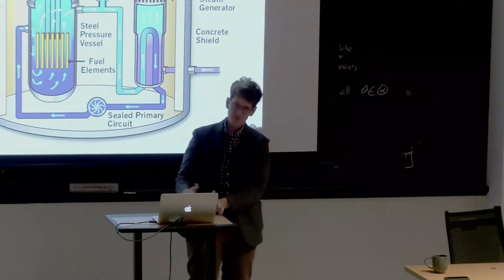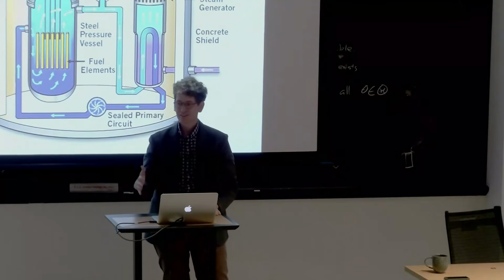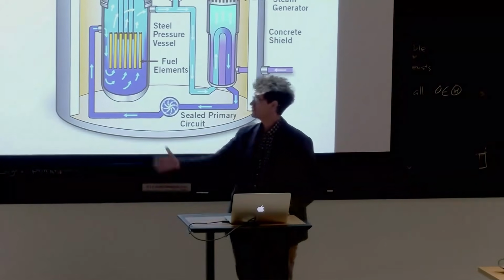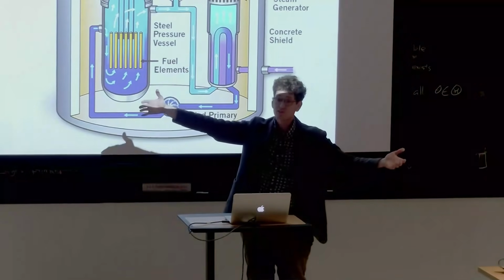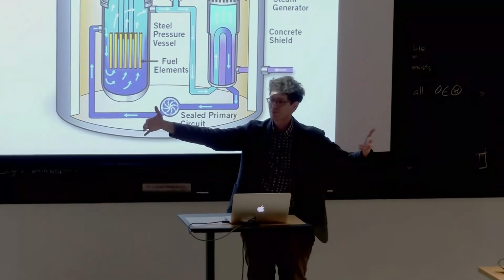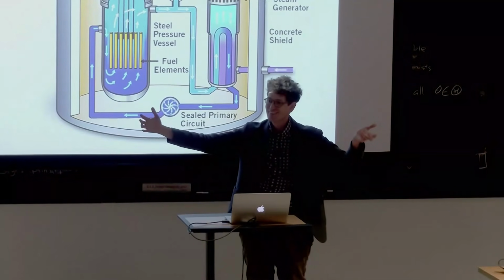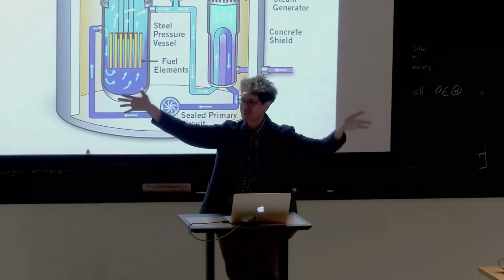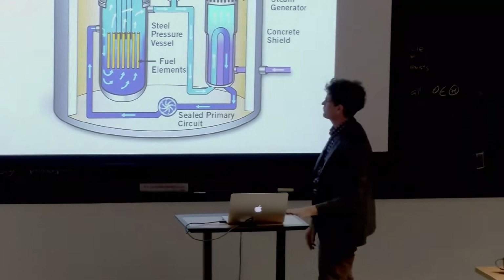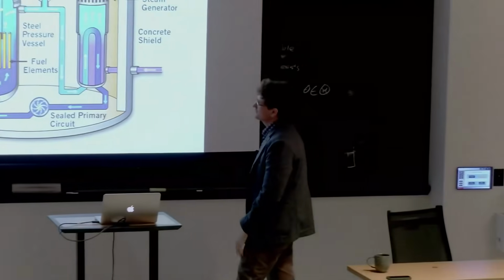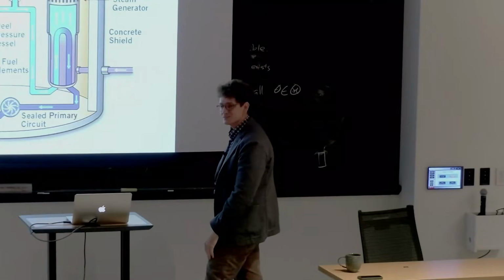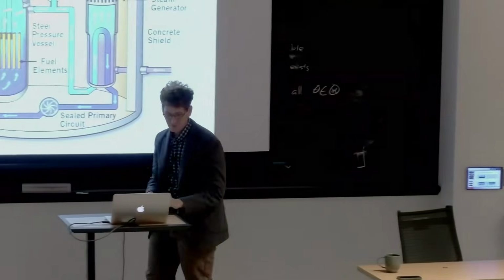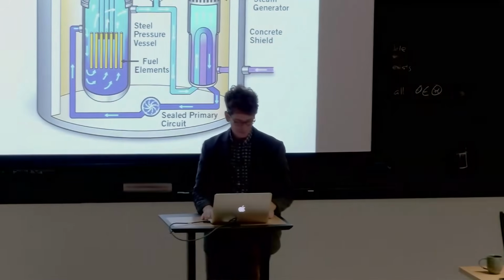So they've given it like a provisional operating license, but they may have to shut the reactor down early. And unfortunately, that cap is so ginormous that you can't actually replace it without disassembling the whole reactor building. This thing has to be built and put in place, and then you build the building around it. And yeah, getting the material science right is really important, and this is what makes these things hard to build.